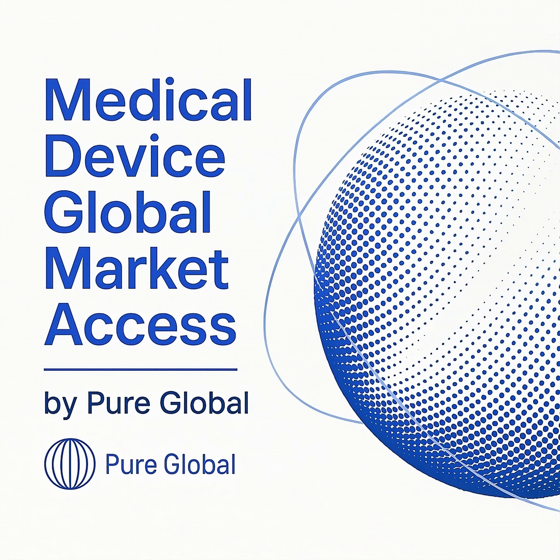This update marked a significant shift, expanding the scope to cover the entire lifecycle of a medical device. It introduced a much stronger emphasis on risk management, not just as a design stage activity, but integrated throughout all QMS processes. The 2016 version also brought increased requirements for the validation of processes, including software validation, and placed a greater responsibility on organizations to control their suppliers and outsourced activities. This ensures quality is maintained across the entire supply chain.